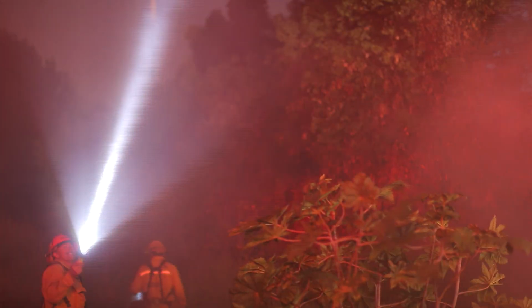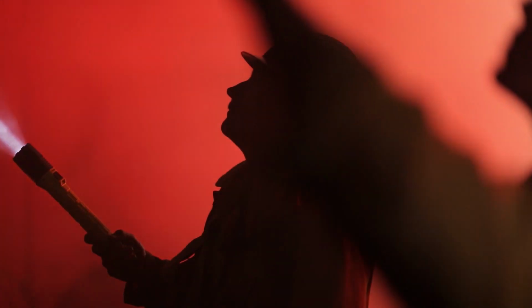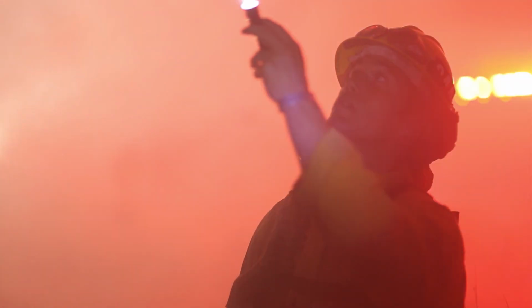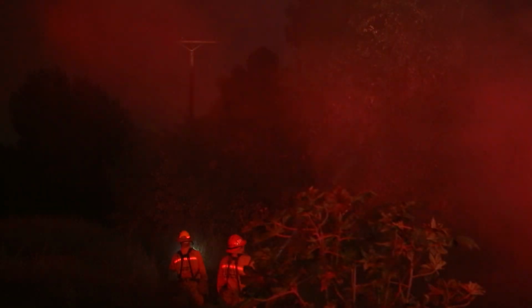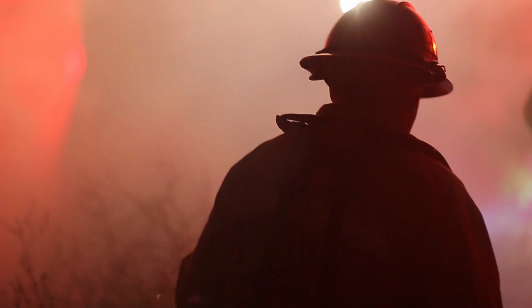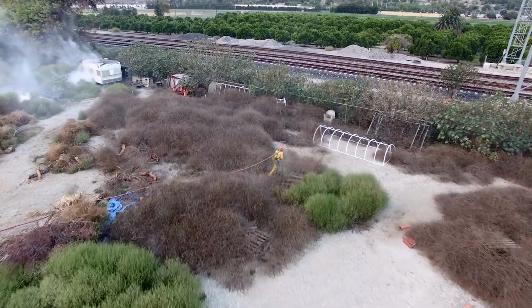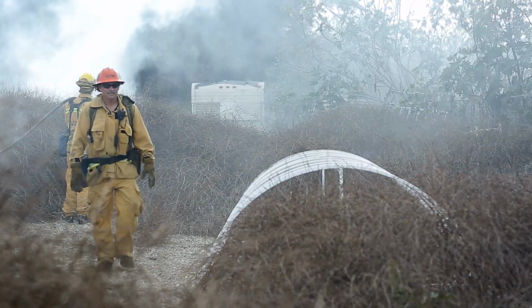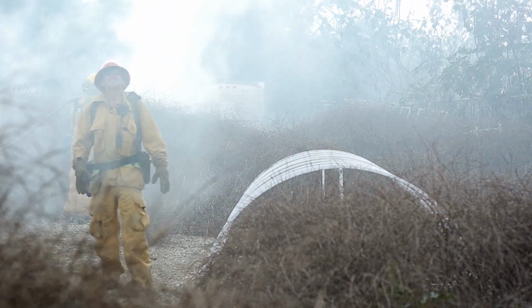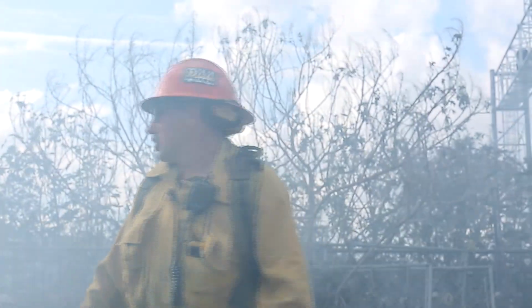At night, use a light to trace all conductors from pole to pole until you've determined the full extent of the damage and the location of all downed wires. Be extremely careful in dense vegetation areas where wires may be camouflaged or hidden, especially at night. As you track the wire's path, locate all wire ends and stay clear.